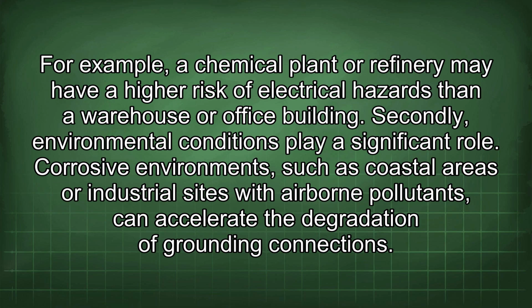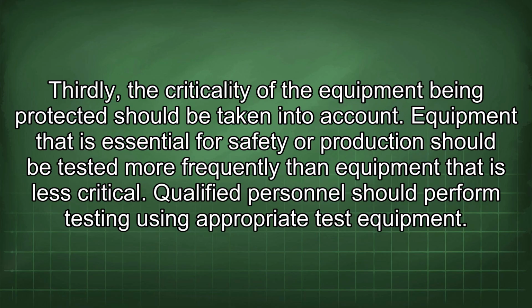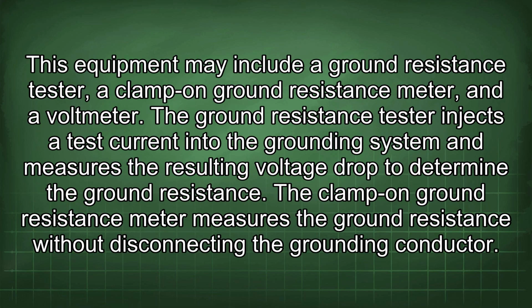Secondly, environmental conditions play a significant role. Corrosive environments such as coastal areas or industrial sites with airborne pollutants can accelerate the degradation of grounding connections. Thirdly, the criticality of the equipment being protected should be taken into account. Equipment that is essential for safety or production should be tested more frequently than equipment that is less critical. Qualified personnel should perform testing using appropriate test equipment. This equipment may include a ground resistance tester, a clamp-on ground resistance meter, and a voltmeter.